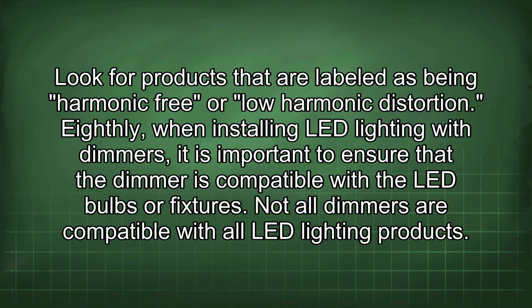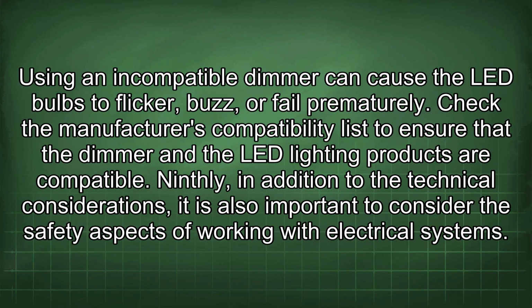Eighthly, when installing LED lighting with dimmers, it is important to ensure that the dimmer is compatible with the LED bulbs or fixtures. Not all dimmers are compatible with all LED lighting products. Using an incompatible dimmer can cause the LED bulbs to flicker, buzz, or fail prematurely. Check the manufacturer's compatibility list to ensure that the dimmer and the LED lighting products are compatible.